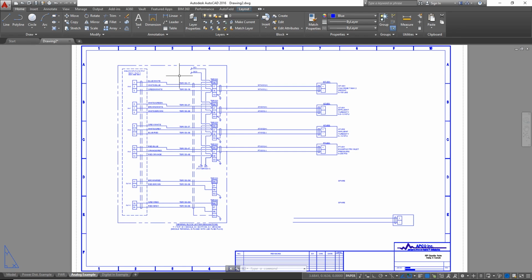You can see here, you've got DC positive and DC negative. This is power coming from another place in our control panel. It's providing power to these terminal blocks in case these instruments out here require power, or loop power as we refer to it. The boxes out here that you see, these four boxes, are representing instrumentation in the field.